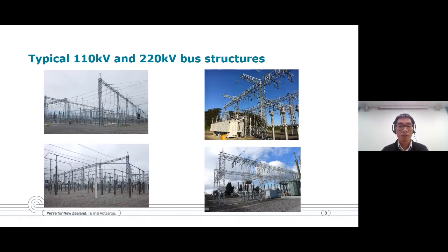I'm pretty sure most people will be familiar with substations and what a bus structure is, but I'll cover it briefly. A typical bus system will have a bus conductor, insulators, and support structures. In Transpower, the 110 and 220 kV structures use lattice gantries as the support structure for strung bus work, and we use concrete support posts for 220 kV rigid bus systems.